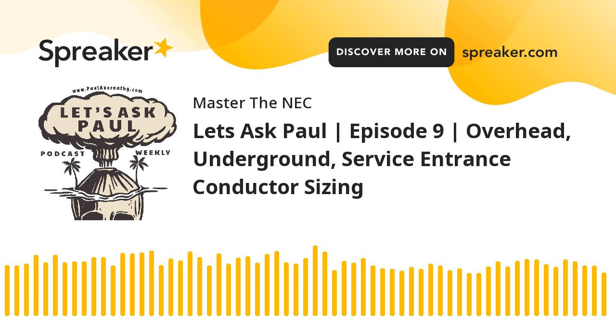They would be service entrance conductors either overhead, or if they were coming underground, let's say you had a transformer pad on your property, and that's where the utility stopped and the line of demarcation, and now you're responsible as an electrician for running those conductors underground to the meter, let's say, then that would be underground service conductors, or depending on how they're run, they could just be underground service entrance conductors. Again, go read the definitions. It's kind of hard for me to show that here in a podcast because that's a visual thing. But again, we're talking about what the electrician has control over, not what we don't have control over.